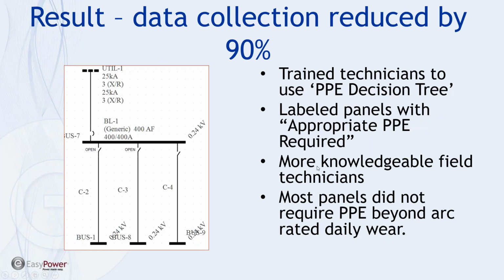So we ended up with more knowledgeable field technicians and potentially eliminated over 90% of the data collection that would have been required had they gone to each panel and collected data and done the study. And as it turns out, most of the panels do not require PPE beyond the daily wear. And I can't even guess how many tens of thousands of dollars he saved in the process. But frankly, I think he deserves a gold star.